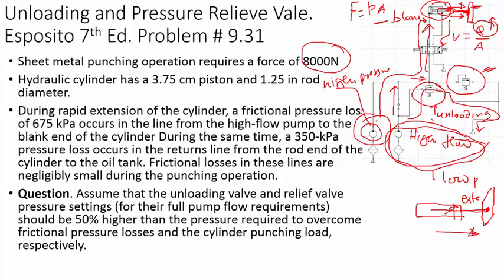On the blank side there is a 675 kilopascal loss, and on the rod end there is a 350 kilopascal loss. When the cylinder is fully extended and touching the sheet metal for punching, it is no longer moving, so there is no fluid friction or loss during the punching operation. However, when the cylinder is moving, there are significant fluid friction losses. Let me calculate those.